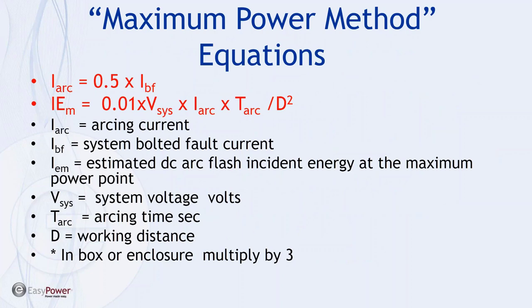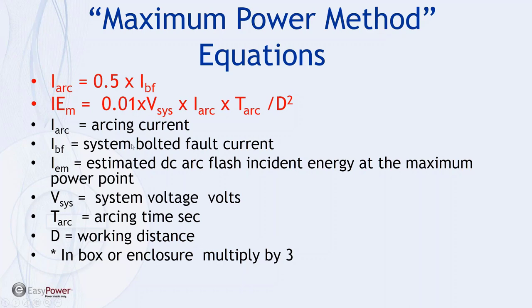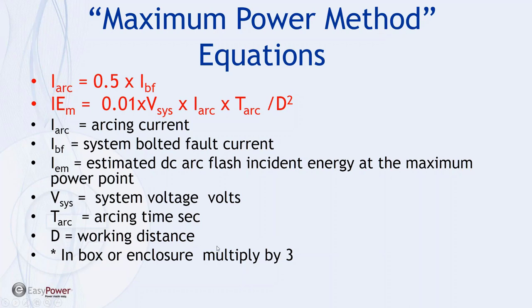So the maximum power method equations basically tell us that the arcing current is 50% of the maximum bolted fault current and that the incident energy is equal to this second equation where we have the arcing current, the system voltage, the estimated arc incident energy to maximum point, the system voltage in V, and the arcing time in seconds, and then the working distance squared. And then if we're looking or talking about a fault in an enclosure, there's a multiplication factor that varies based upon which study you're looking at, but it's roughly a 3x type of multiplication effect.